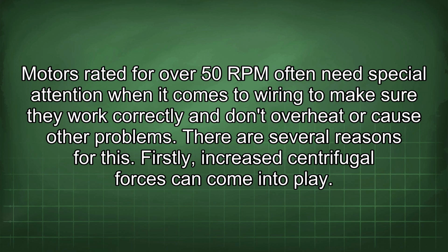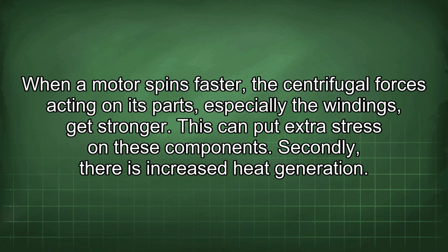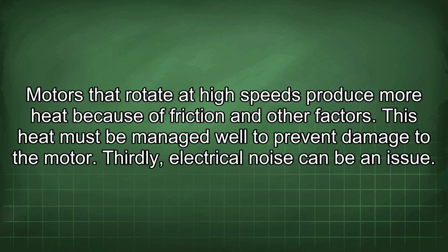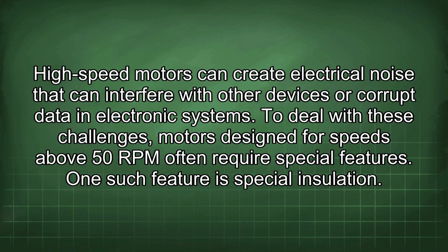Firstly, increased centrifugal forces can come into play. When a motor spins faster, the centrifugal forces acting on its parts, especially the windings, get stronger. This can put extra stress on these components. Secondly, there is increased heat generation. Motors that rotate at high speeds produce more heat because of friction and other factors. This heat must be managed well to prevent damage to the motor. Thirdly, electrical noise can be an issue. High-speed motors can create electrical noise that can interfere with other devices or corrupt data in electronic systems.